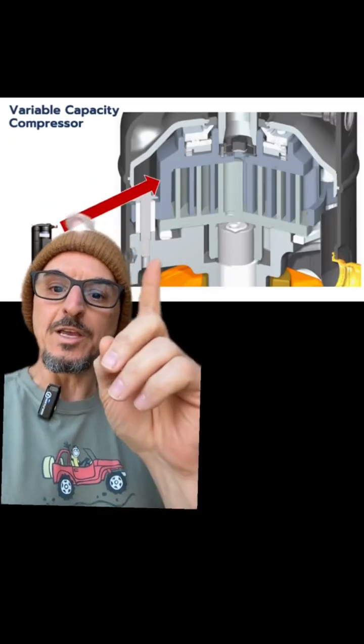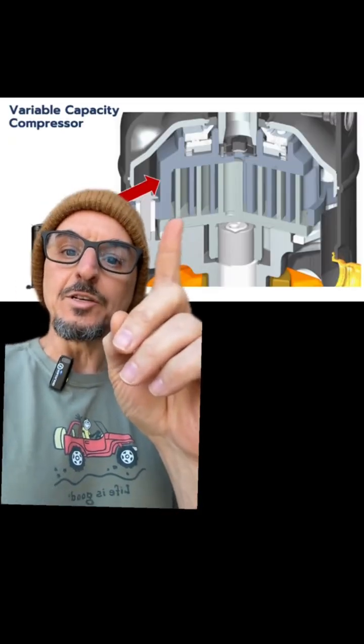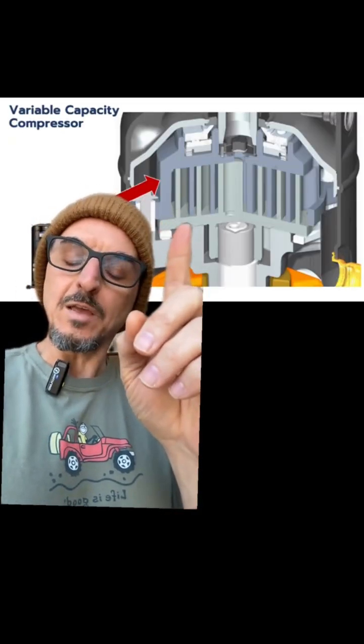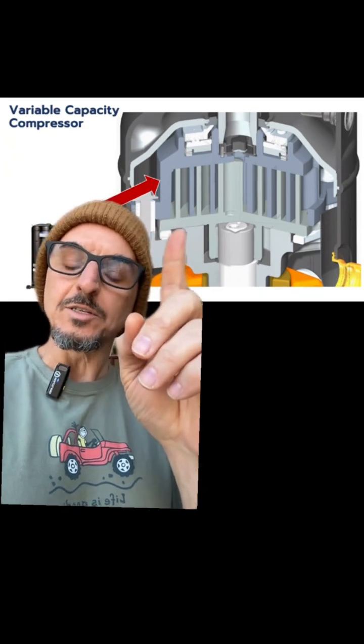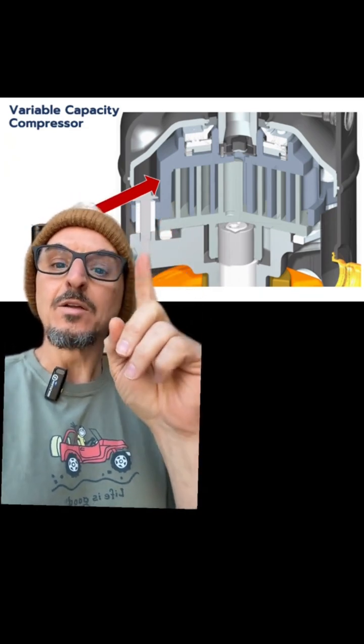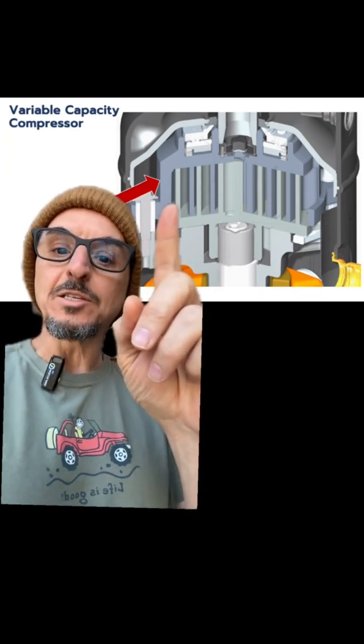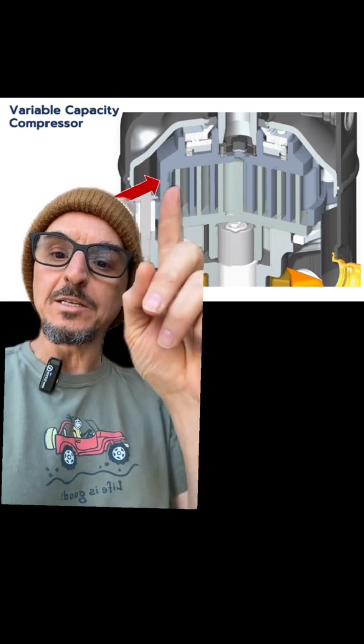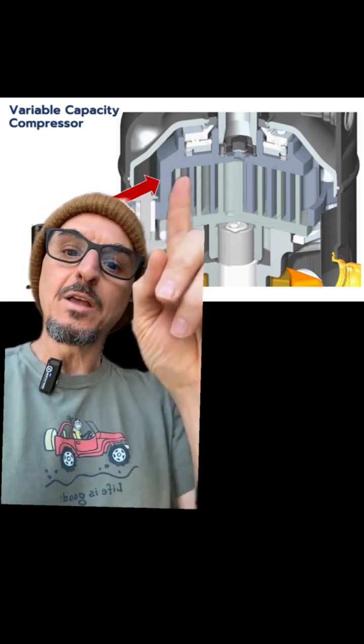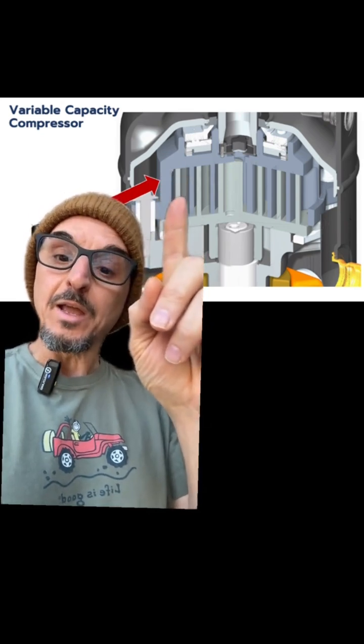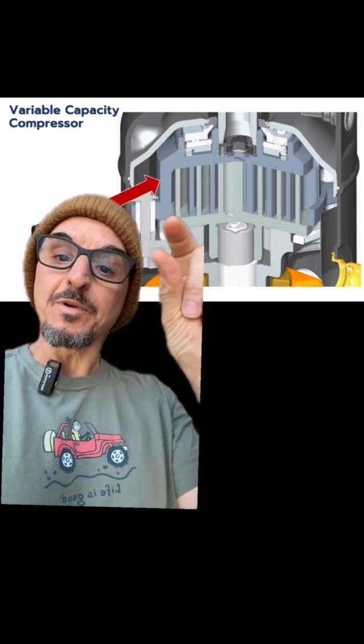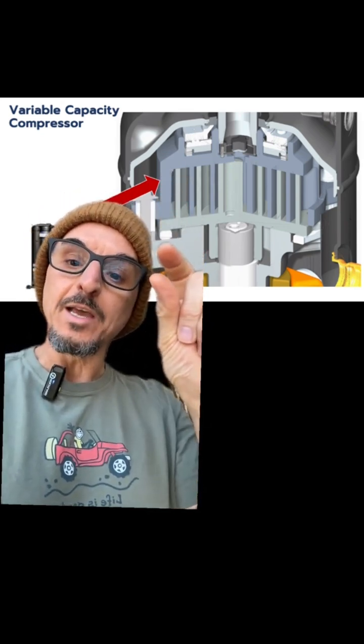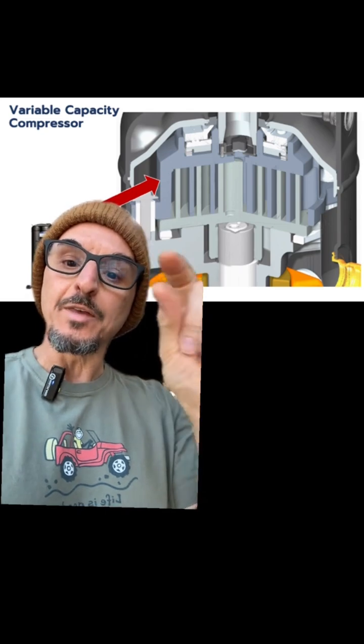Let's look inside. There's the inside of a digital scroll compressor — it looks the same as a scroll compressor. What happens when you want to reduce the capacity is the top plate is lifted from the bottom plate. And when they're separated by a very small amount, it doesn't do any work on the compressor.